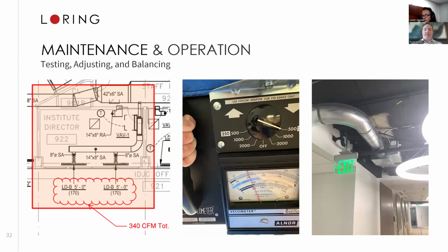Testing, adjusting, and balancing is critical to making sure that you have the correct flow rates in a space. So just because on the design drawing, when we design a new HVAC system, say, we call for a certain amount of airflow CFM or water flow gallons per minute, we want to make sure that what the BAS system that the building engineers are relying on is seeing is actually happening.